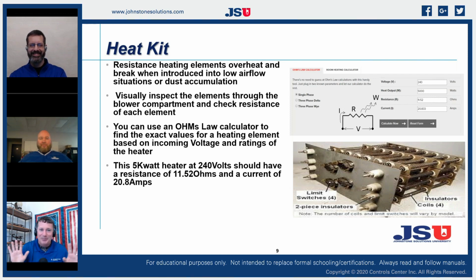Get that, don't believe me, we get that call once in a while. It's a horseshoe setting. So we put it on ohms so that we can read the resistance across it, and it's going to be in that ballpark, 11.5 or so. So by checking ohms, we can check the integrity of our element without even having applied voltage on it.